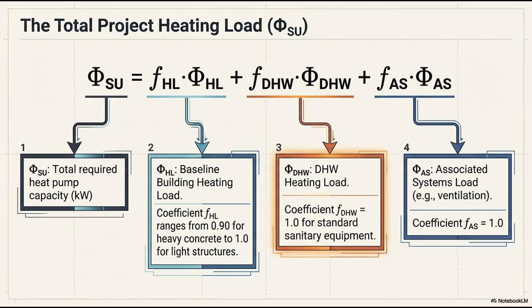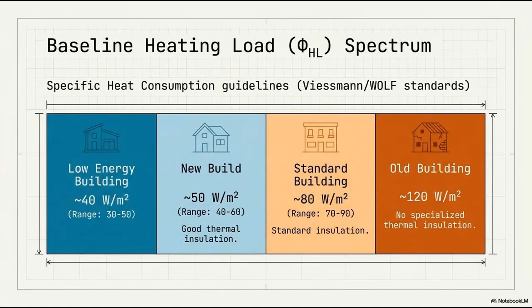The next massive energy draw in Formula 6.1 is domestic hot water. And reading through the engineering docs dealing with a hot water load forces a major strategic choice onto you as the homeowner. Yeah, two very distinct paths emerge in the source material here. You've got maximum accumulation versus partial accumulation, and they both dictate entirely different mechanical setups and, well, daily operations.